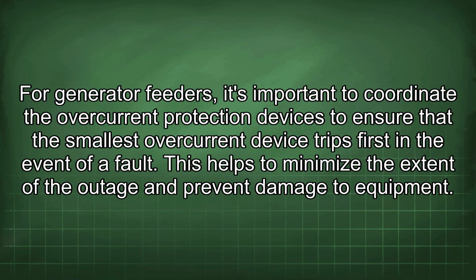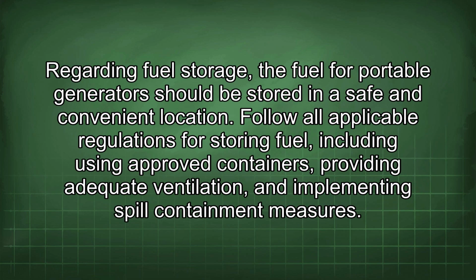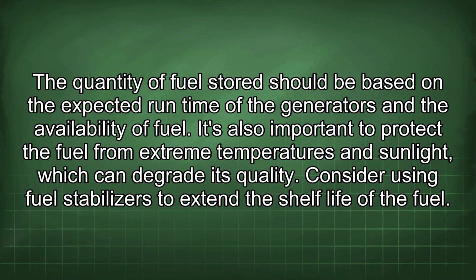For generator feeders, it's important to coordinate the overcurrent protection devices to ensure that the smallest overcurrent device trips first in the event of a fault. This helps to minimize the extent of the outage and prevent damage to equipment. Regarding fuel storage, the fuel for portable generators should be stored in a safe and convenient location. Follow all applicable regulations for storing fuel, including using approved containers, providing adequate ventilation, and implementing spill containment measures. The quantity of fuel stored should be based on the expected runtime of the generators and the availability of fuel. It's also important to protect the fuel from extreme temperatures and sunlight, which can degrade its quality. Consider using fuel stabilizers to extend the shelf life of the fuel.